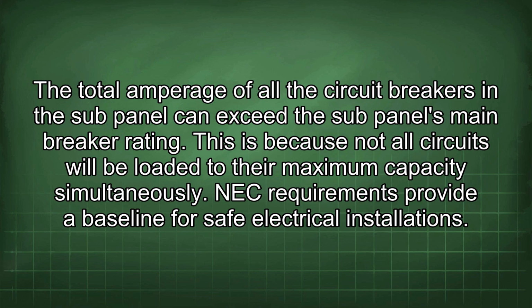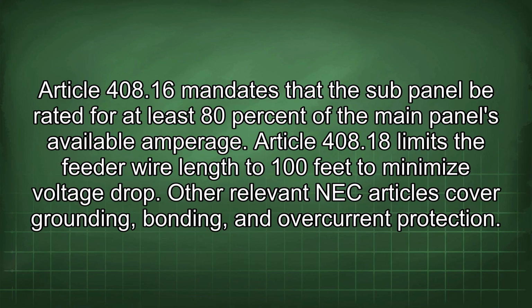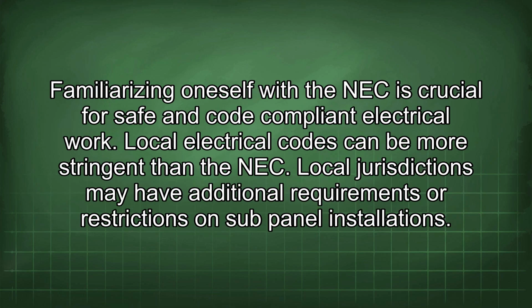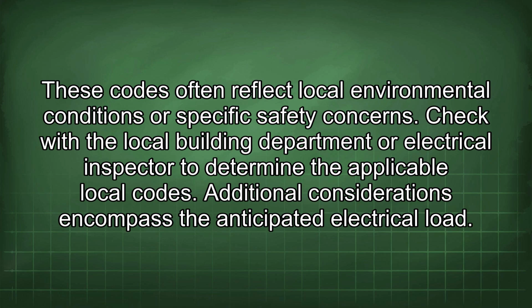NEC requirements provide a baseline for safe electrical installations. Article 408.16 mandates that the sub-panel be rated for at least 80% of the main panel's available amperage. Article 408.18 limits the feeder wire length to 100 feet to minimize voltage drop. Other relevant NEC articles cover grounding, bonding, and overcurrent protection. Familiarizing oneself with the NEC is crucial for safe and code-compliant electrical work. Local electrical codes can be more stringent than the NEC. Local jurisdictions may have additional requirements or restrictions on sub-panel installations. These codes often reflect local environmental conditions or specific safety concerns. Check with the local building department or electrical inspector to determine the applicable local codes.